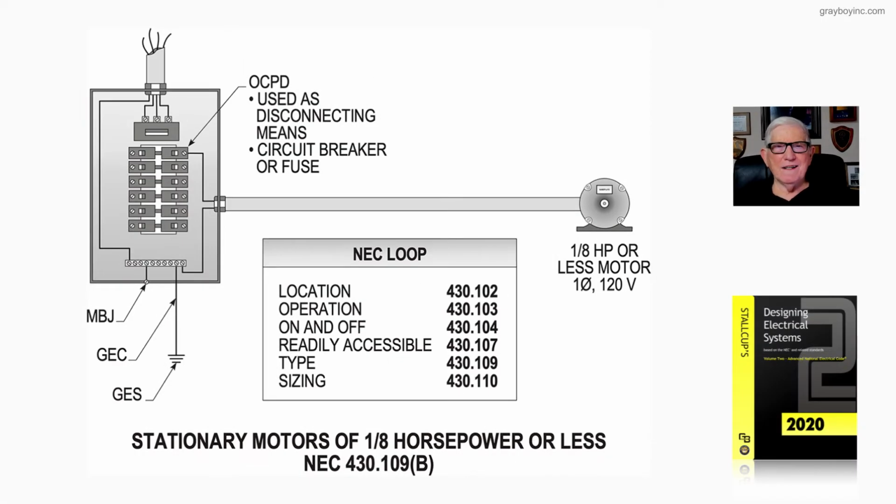Now this figure 18-42 is illustrating when a motor is, say, 1/8 horsepower or less, the disconnect in the service equipment or sub panel could be used to disconnect this motor. You know, maybe like a clock on a wall becomes under this rule.